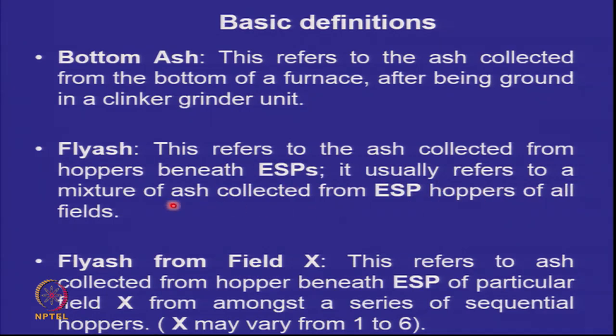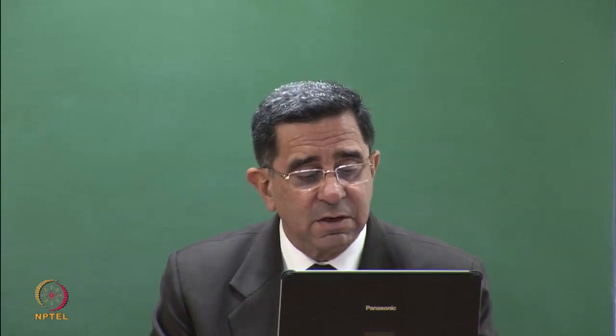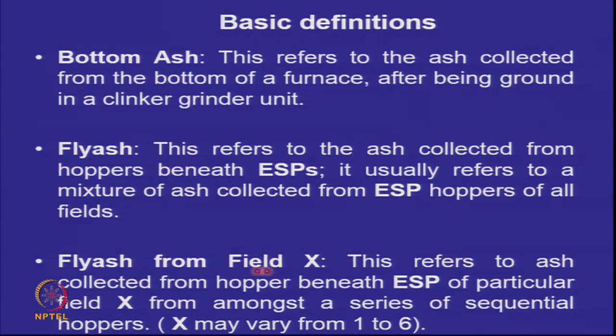Fly ash is the mixture of ash collected from all the hoppers beneath the ESPs. With 5 or 6 fields, the ash produced varies in size from coarser in field 1 to finer in field 6. When sending ash to a pond, all fields are typically mixed together, though they can be collected individually. When the term 'fly ash from field X' is used, it refers to ash from the hopper of that specific field; the finest ash with the finest particles comes from field 6.